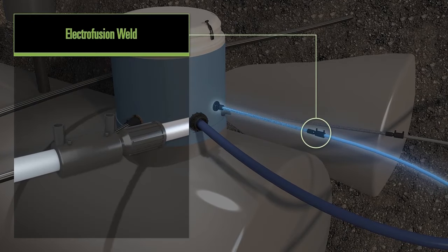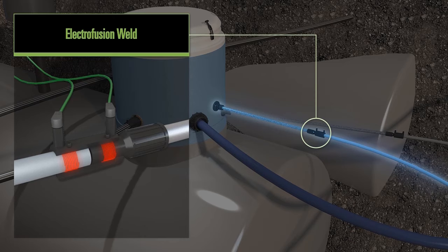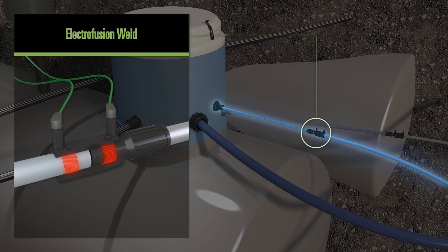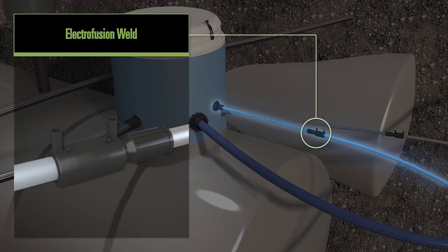A conduit is a channel or tube that protects electric wiring in the station environment. It's constructed of high-density polyethylene, which means it is strong and flexible and can be used continuously throughout the fuel station and withstand more than conventional conduit. Again, we use the electrofusion welding installation process, like what we do with the UPP brand semi-rigid pipework, to join electrical conduit to each other and when entering the sump for a seamless and watertight connection.